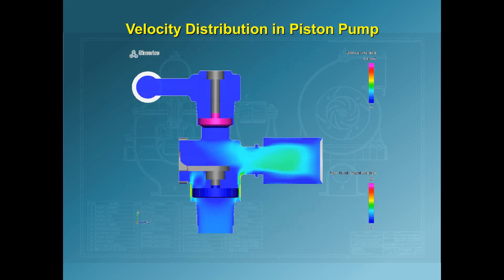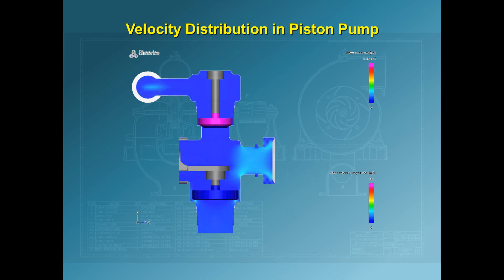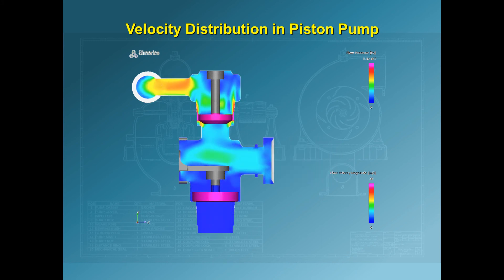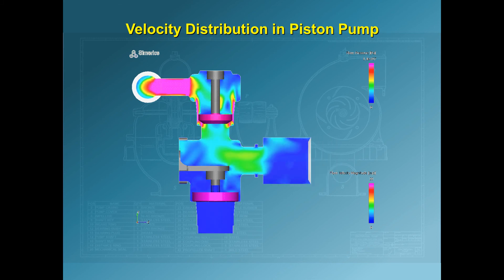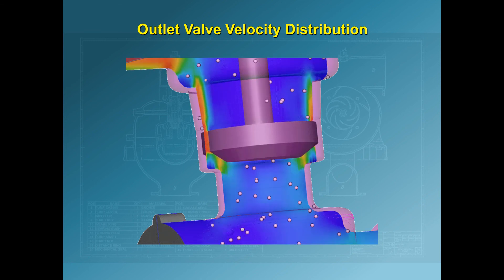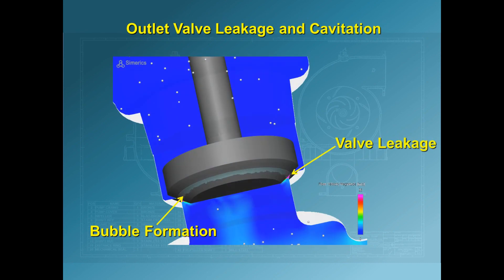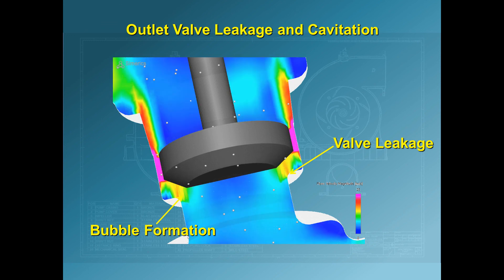Here is the velocity distribution. Notice the fluid jetting past the valves as they open. In this simulation, the inlet valve is modeled as if it closed perfectly, but the outlet valve was intentionally made to close only partially, which is a realistic effect. This is a close-up of the velocity distribution near the outlet valve. When the outlet valve closes, fluid leaks downward, causing the pressure to drop and bubbles to form.